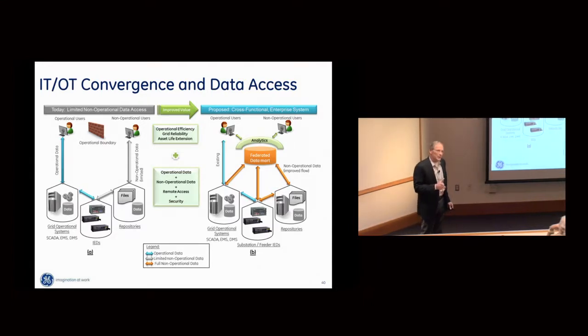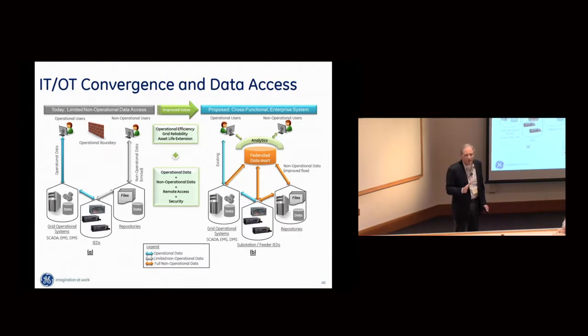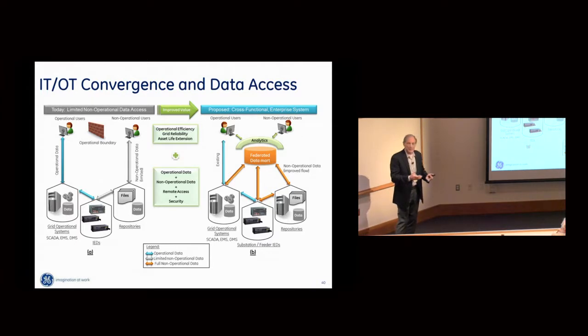Here's what really kills me: there are 52,000 distribution substations in the U.S. Only 2/3 of those today have any kind of automation installed at distribution. We have an observability issue. What really kills me is of the 2/3 that have automation installed, half of those automation devices are operating standalone. Even though they have two-way communication capability and valuable information inside, they're operating like an electromechanical device, a standalone device. We're not using the communications to get that data upstream.